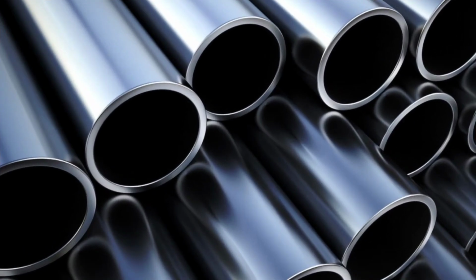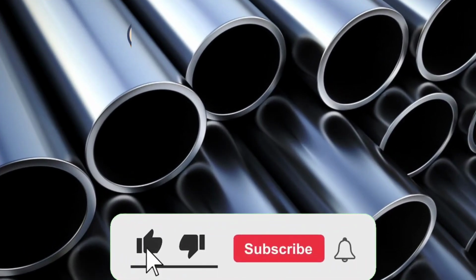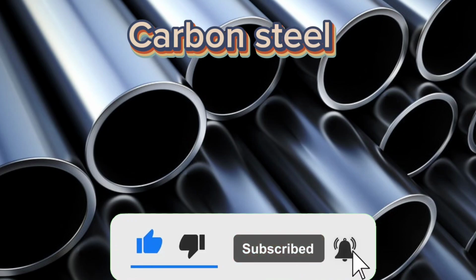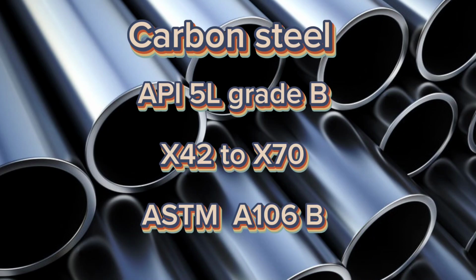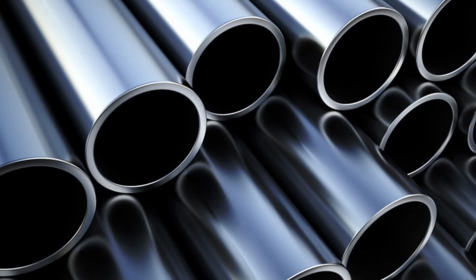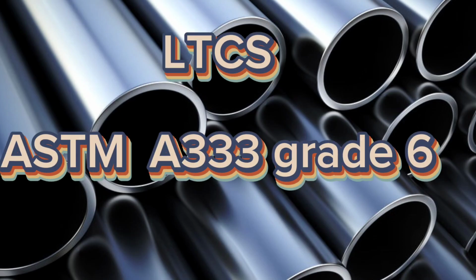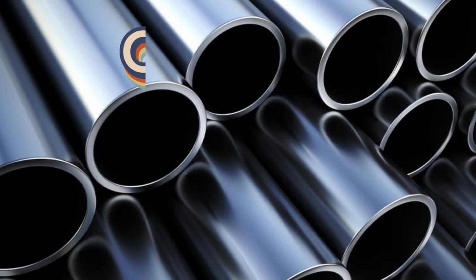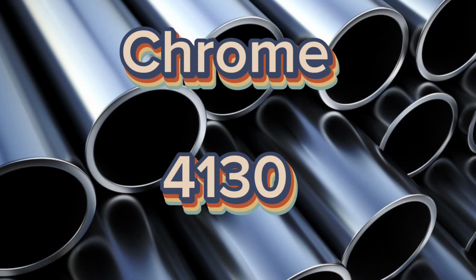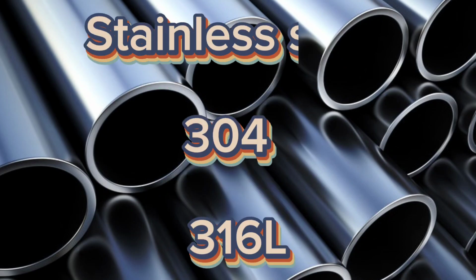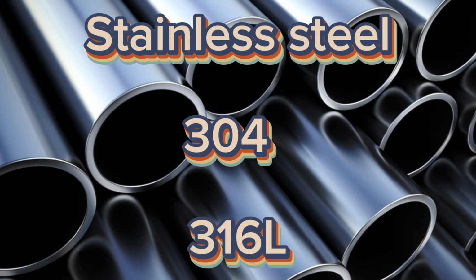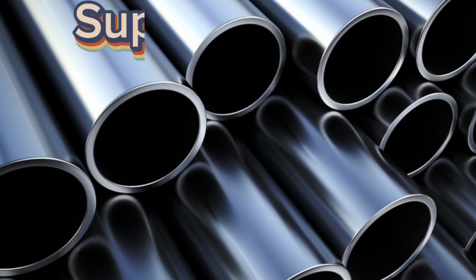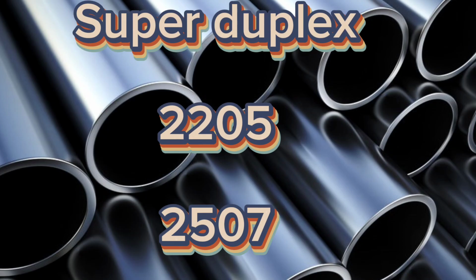Pipes with the following composition are mostly used in production. Carbon steel pipe material grades are API 5L grade B, X42 to X70, and ASTM A106B. Low-temperature carbon steel pipe material grade is ASTM A333 grade 6. Chromium molybdenum pipe material grade is alloy steel 4130. Stainless steel pipe material grades are 304 and 316L. And super duplex pipe material grades are 2205 and 2507.